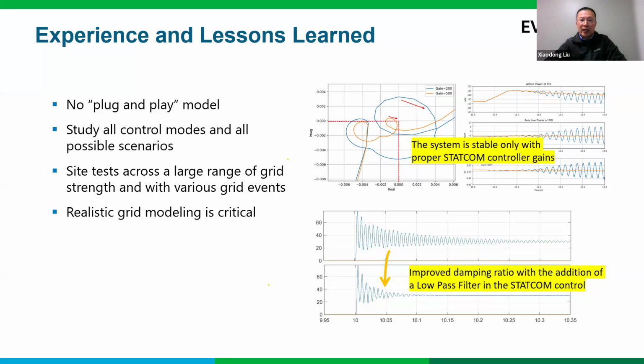At the screening and preliminary study stage, normally a range of control parameters is determined, which will save you a lot of time in the following studies. For example, the diagram on the right shows your STATCOM will be unstable in the weak grid with a controller gain in a certain range, and this range should be avoided in the following studies. Non-ideal performance of the model should be discussed with the manufacturer to get it resolved, the sooner the better.